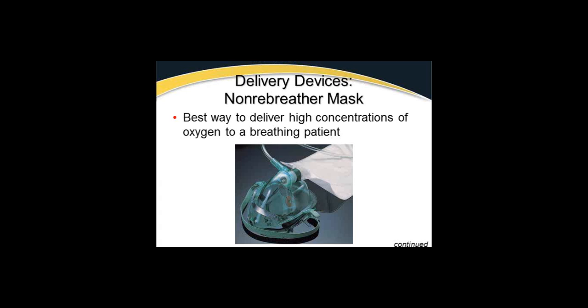The patient takes a breath that opens the flapper valve on the top of the bag there and allows them to draw air or draw oxygen out of that bag. Then they exhale. When they exhale, it closes that flapper valve on the top of the reservoir bag and opens the flapper valves on the side of the mask to exhale.